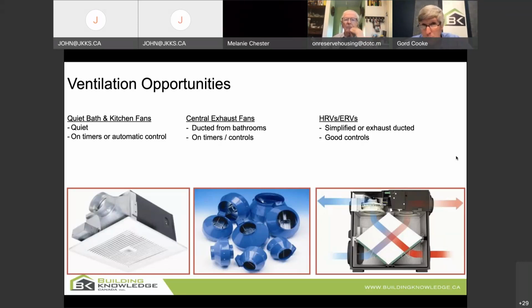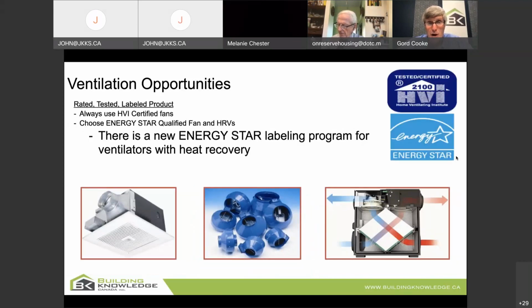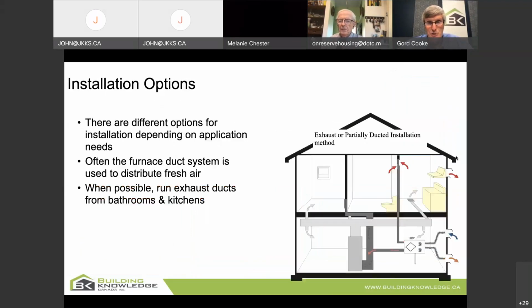And many great fans from Broan, NuTone, Panasonic now have 2-speed fans. So you run the fan at low speed all the time, and then when somebody goes into the bathroom, they either flick the switch or there's an occupancy sensor that says, let's go to high speed. You could even think in the middle about a central exhaust fan, a fan that takes air from, say, 2 bathrooms or the bathroom and the kitchen. That'd be fine too. So all your houses need capacity for ventilation. They don't have to be an HRV or ERV, but at least a good, quiet fan is what you like to get to. And as I say, look for an Energy Star labeled fan, and that's going to get you good performance.